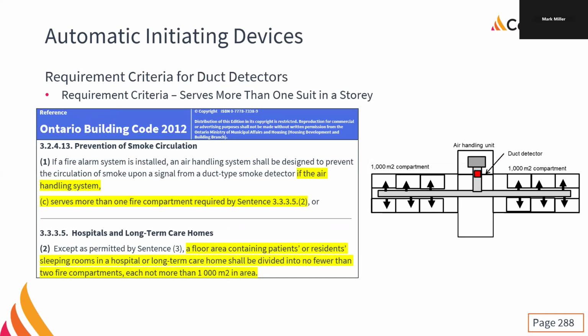Then if we have more than one smoke compartment, right? If we've got more than one zone being served by the air handling unit, right? If we've got 2 wings, the north wing and the west wing of a building, and each of them exceeds the maximum allowable area limit that we saw back in two classes ago. Right, there's a maximum amount of area they can have in a fire zone. If we're more than that, then we're gonna have to put in a duct smoke detector because again, we're not gonna know where the smoke is coming from.